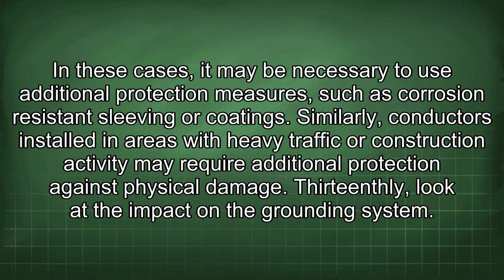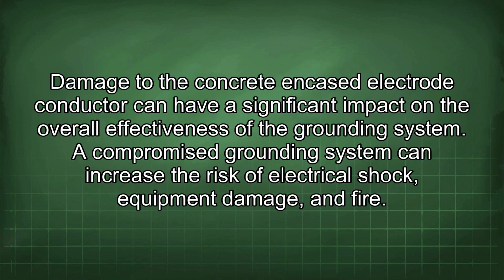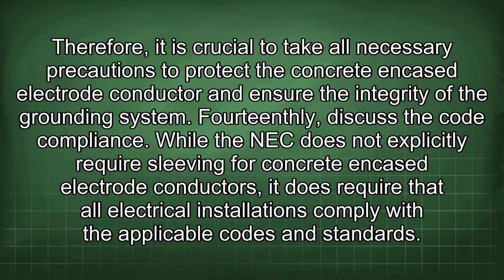13thly, look at the impact on the grounding system. Damage to the concrete encased electrode conductor can have a significant impact on the overall effectiveness of the grounding system. A compromised grounding system can increase the risk of electrical shock, equipment damage, and fire. Therefore, it is crucial to take all necessary precautions to protect the concrete encased electrode conductor and ensure the integrity of the grounding system.